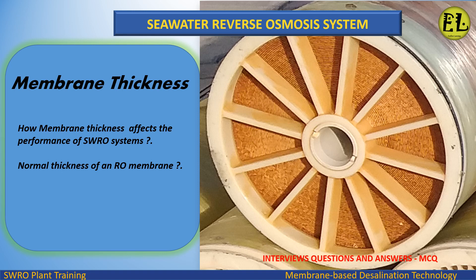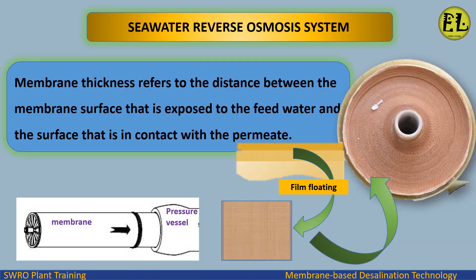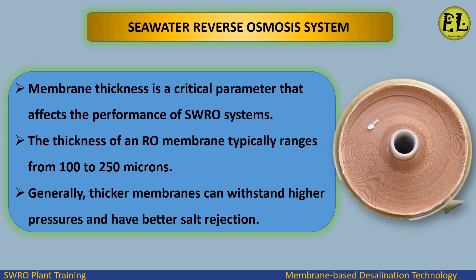Membrane thickness refers to the distance between the membrane surface exposed to the feed water and the surface in contact with the permeate. Membrane thickness is a critical parameter that affects the performance of SWRO systems. The thickness of an RO membrane typically ranges from 100 to 250 microns.